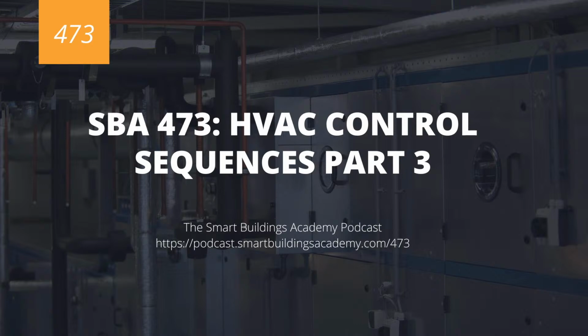So a single path air handler constant volume is going to have fan safeties, just like an actual VAV air handler. And this throws a lot of people because people are like, why do we have high static and low static for a fan if it's a constant volume fan? Well, that's because downstream effects on that system can affect the fan and cause overpressurization or underpressurization issues.